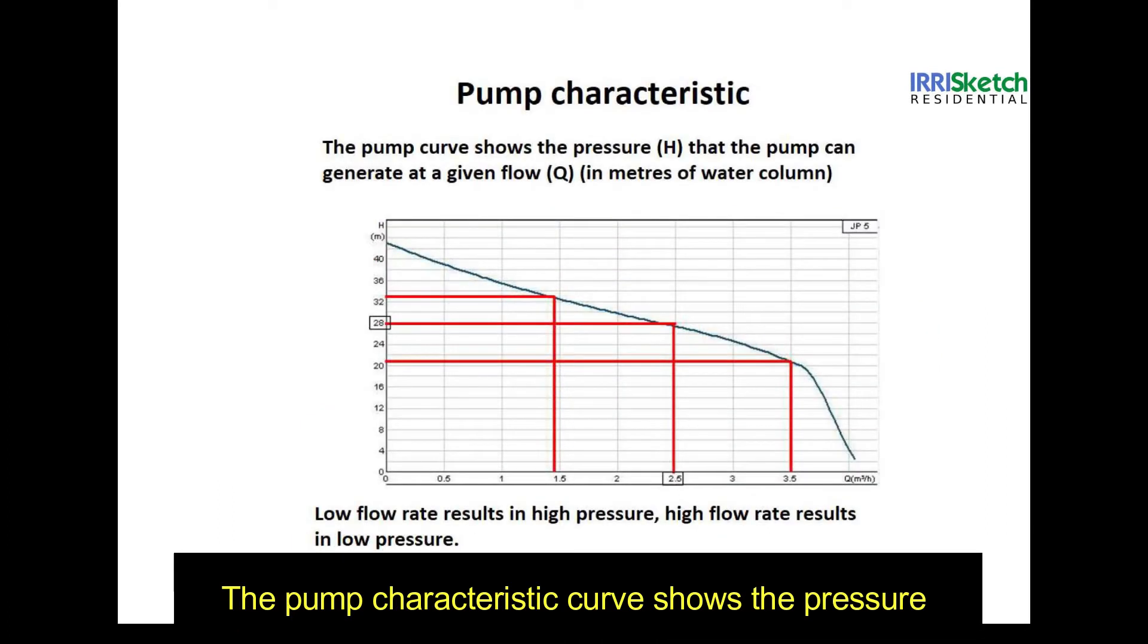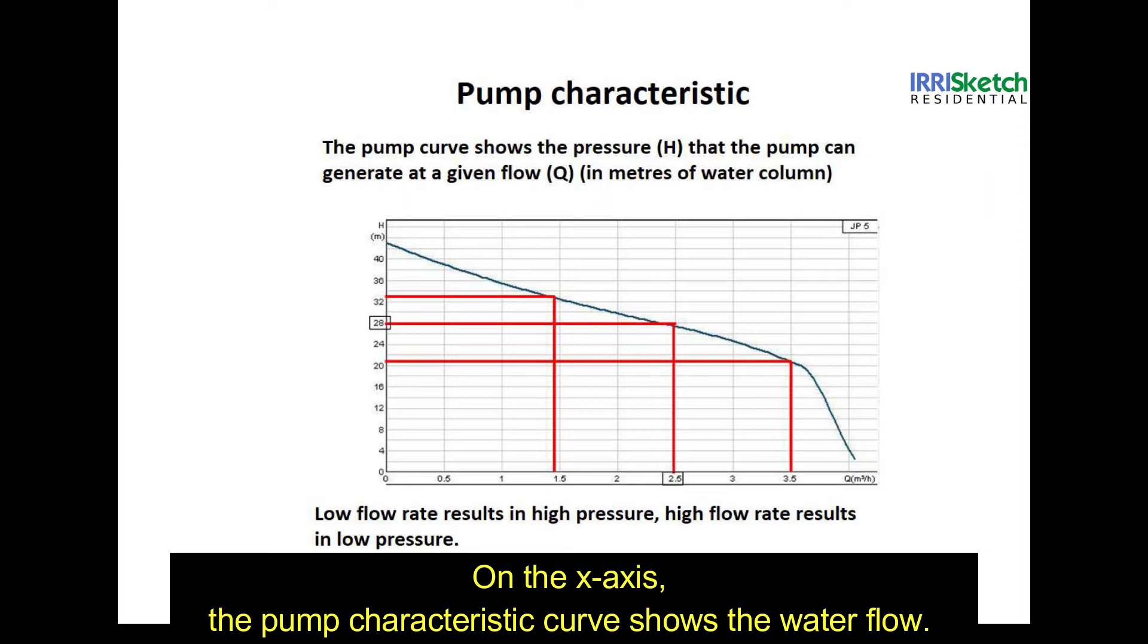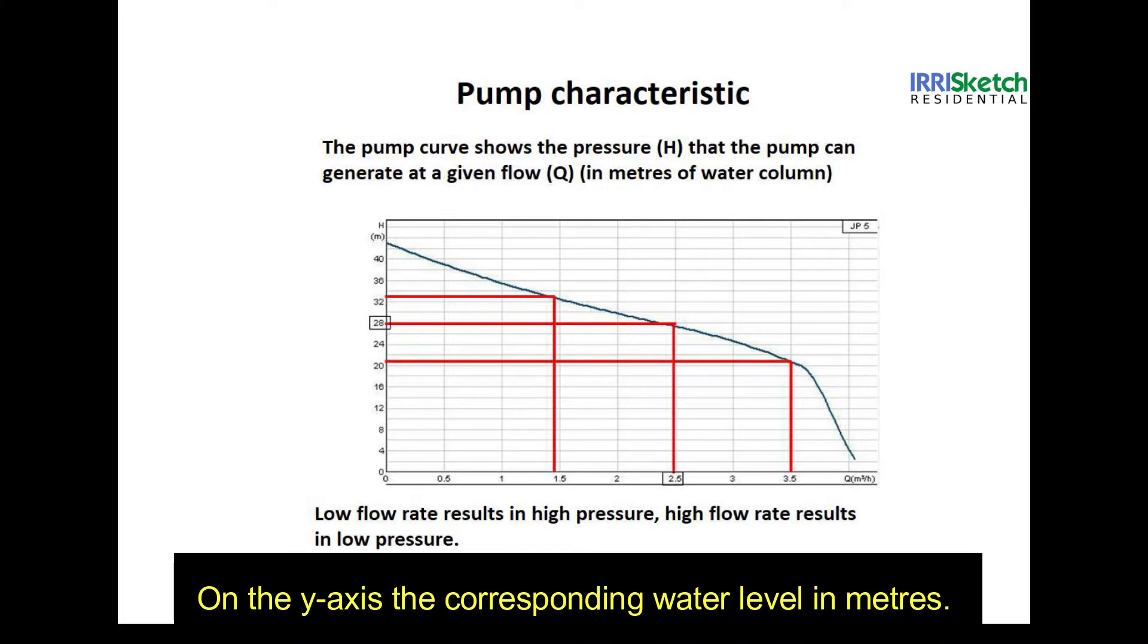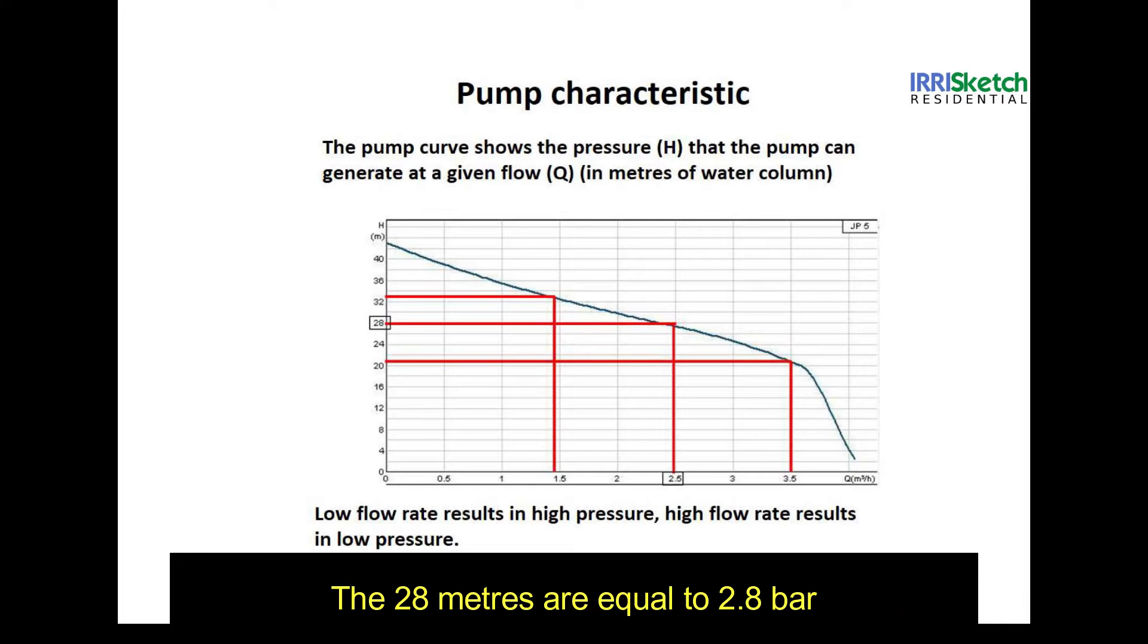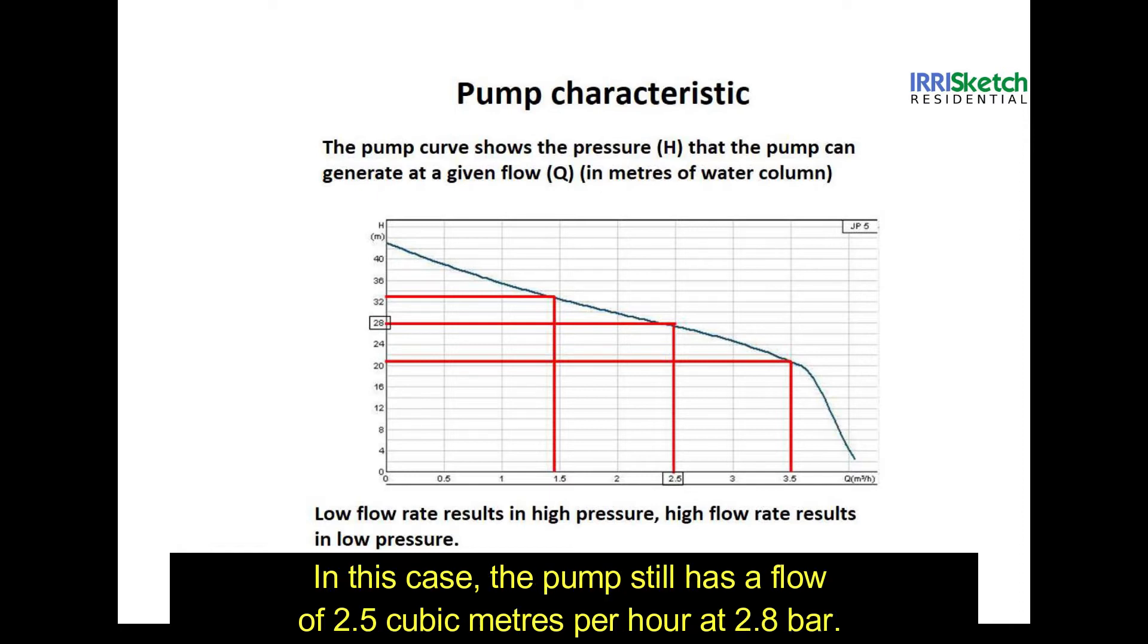The pump characteristic curve shows the pressure that the pump can generate at a given flow rate. On the x-axis, the pump characteristic curve shows the water flow. On the y-axis, the corresponding water level in meters. The 28 meters are equal to 2.8 bar. For every 10 meters of water column, one bar of pressure increases.